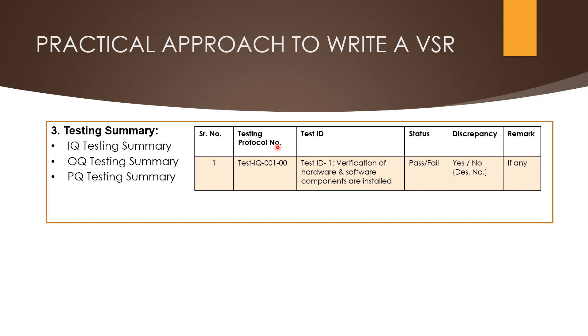Here you can see I have given an example to provide the relevant details with respect to the IQ testing summary. There will be a testing protocol number, and test IDs — for example, test ID 1 is verification of hardware and software components installed, its status whether pass or fail, discrepancy status whether yes or no, the discrepancy number, and a remarks column for any additional notes. Likewise you can mention the OQ protocol testing summary and PQ testing summary.